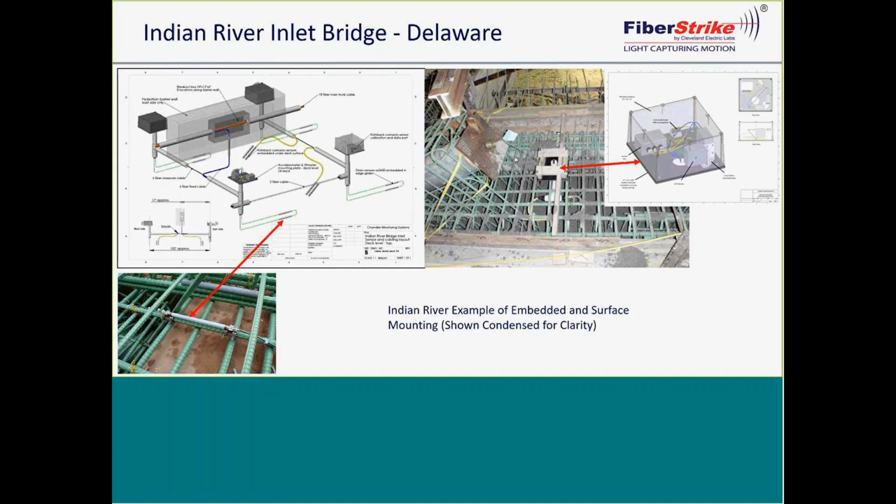And then also wherever we exited from that deck, we had deck plates in 14 dual locations. When I say 14 locations, there were two, one across from each other. We placed tilt sensors, accelerometers, and then also arrayed between, there might be 40, 50 feet in between each one of these boxes. We did not run PVC conduit throughout the deck. It was just at the entryways. The cable was made special so that it can be placed directly into the concrete.